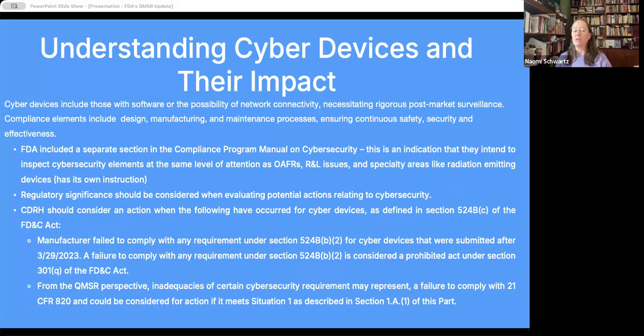So what are these cyber devices and what's the impact? Cyber devices include any medical device that contains software or the possibility of network connectivity or a potential for a vulnerability, which means does it contain software? So those two are somewhat redundant. This necessitates rigorous post-market surveillance on your part. It means that you have to consider design, manufacturing, and maintenance processes, ensuring the continuous safety, security, and effectiveness of your devices. That is the impact of 524B, and that is going to be what FDA is looking for in your archives, in your evidence, in your design history files when they do an inspection, if they focus on cybersecurity elements. That separate section in the compliance program manual details these things.